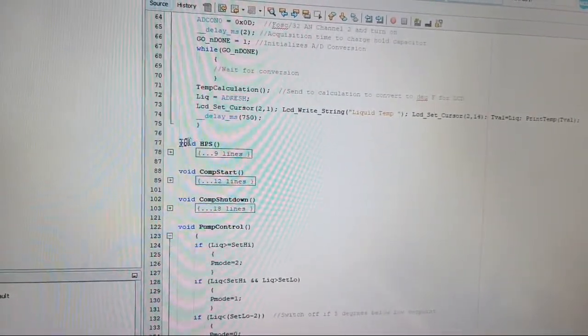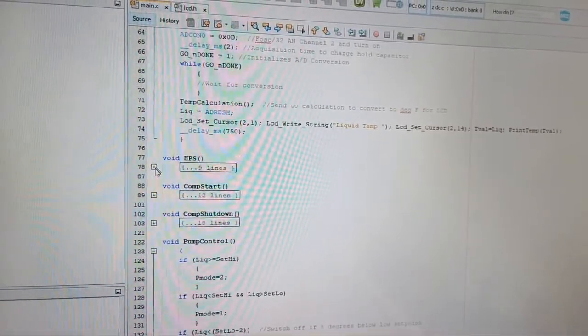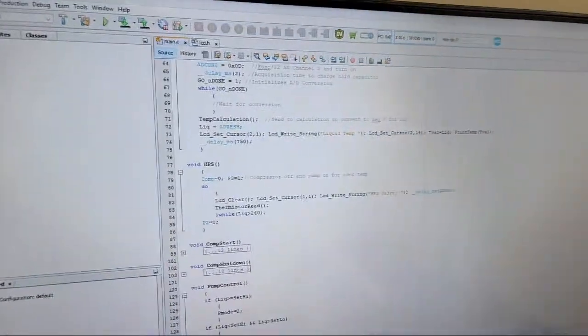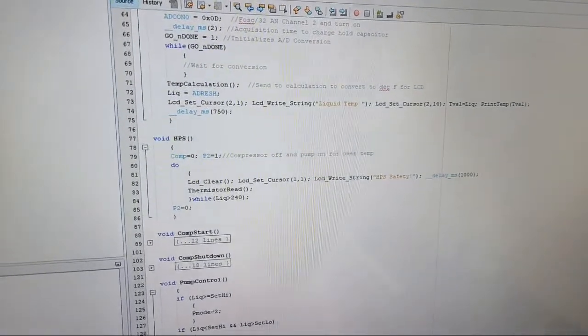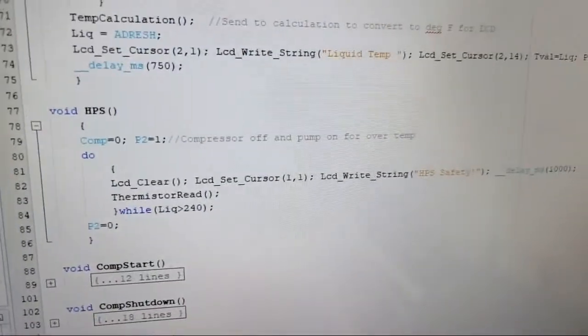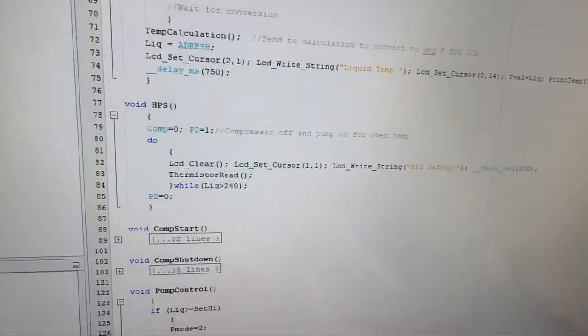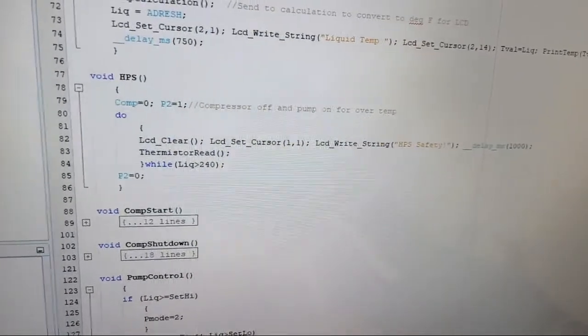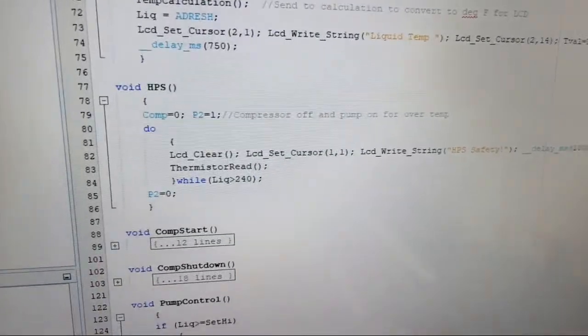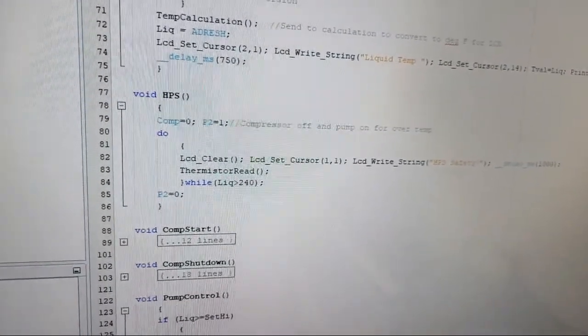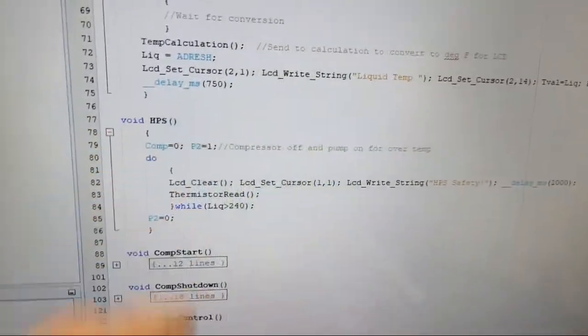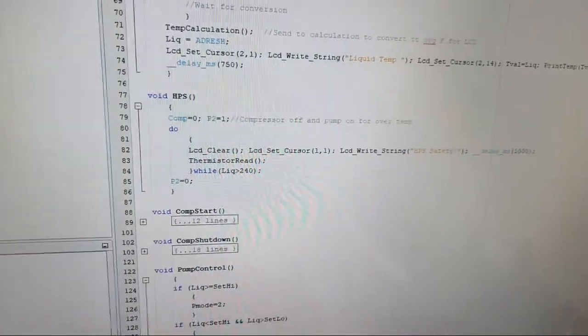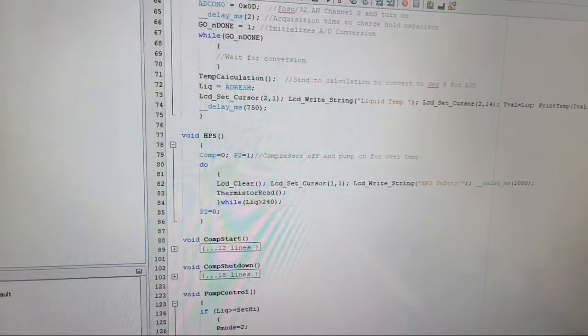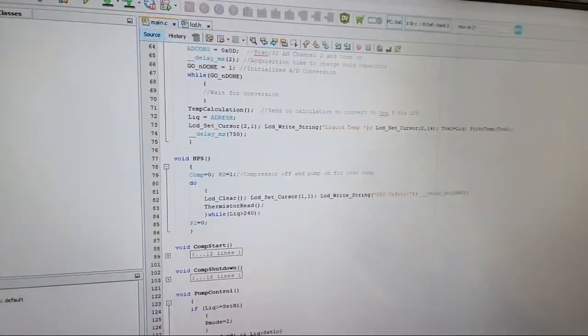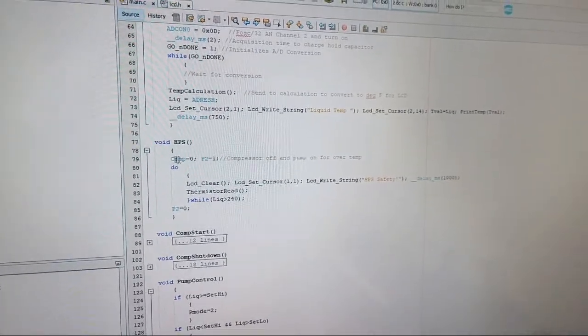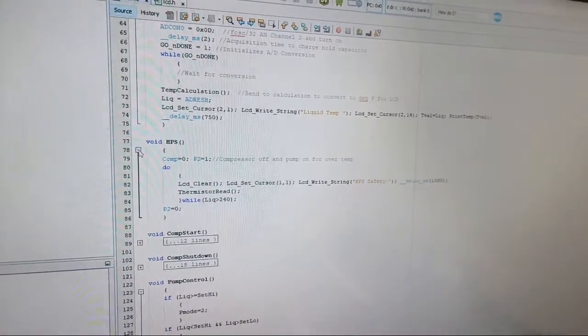So yeah, I got a function for high pressure, and since I only have so many inputs, I just break my thermistor, which will shoot my value up to like 250 or something. So if the value goes above here, which I'm never going to read 240 degrees on the liquid line normally, ever, if it hits that, I just know that the high pressure switch opened out there. I have it turning the pump on, and it also stops the compressor. So, safety. I don't remember if I ever finished all the code. Well, it'll stay in there until that drops below there, so it works. And it just keeps saying that it's in high pressure safety.